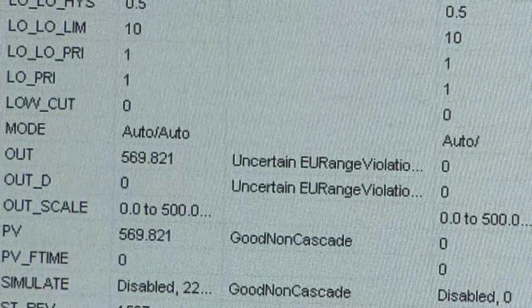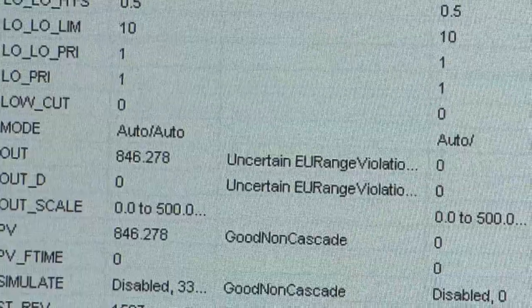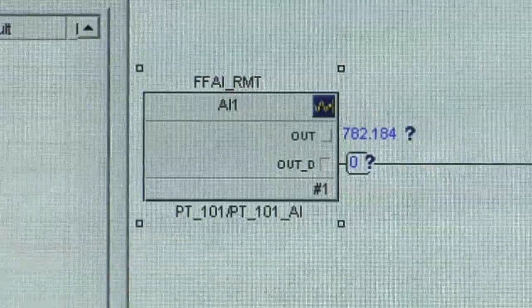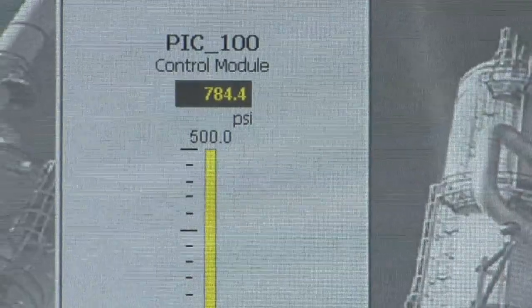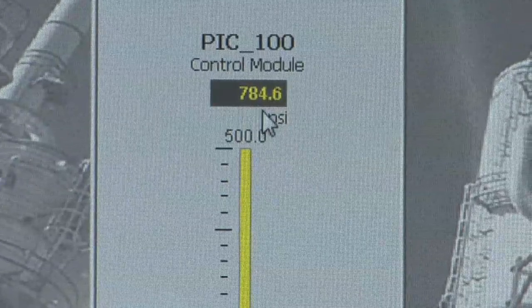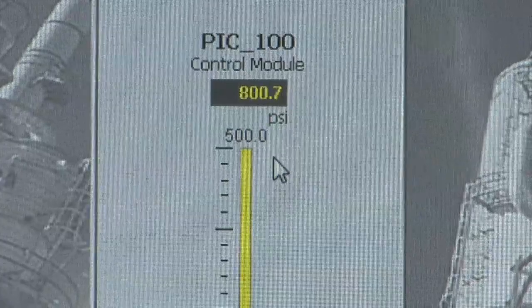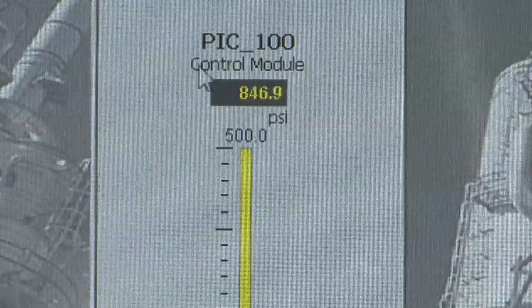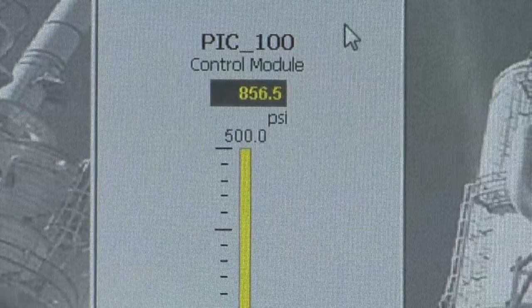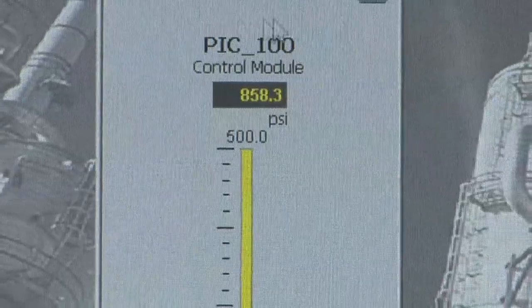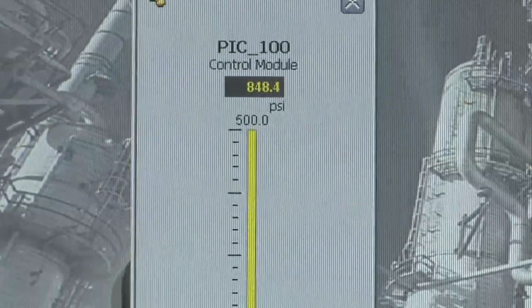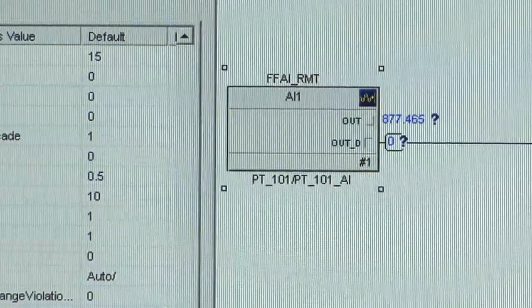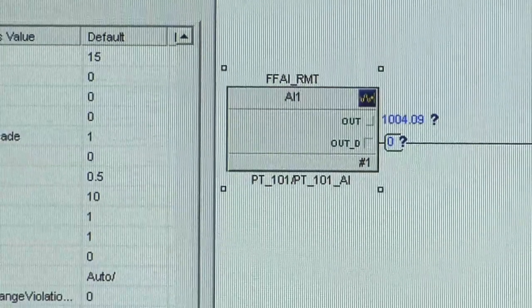You can see it's actually turned blue here, and that's telling us that the value has exceeded our scale. We can go back to the operate view and we see that we're now at 784. Now, while the scale itself has maxed out, we are still actually getting a value, so the operator will know what we are seeing the entire time even as it is beyond our scale limit. We'll have Chuck increase it once again to see if we can go beyond the capabilities of the instrument capsule itself.